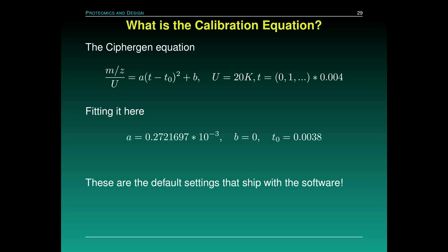Well, actually, there's something rather odd about this set of parameters. The reason I guess these is that these are the default settings that ship with the software. So it's not that they haven't been calibrated in 4 months. These spectra that have been posted have never been calibrated at all. So we think that there is a problem here.